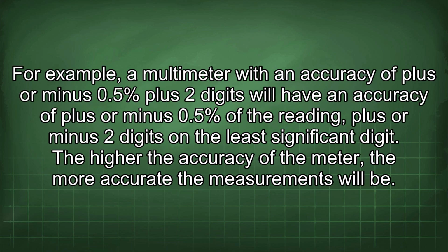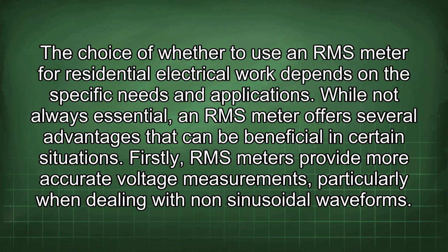For example, a multimeter with an accuracy of plus or minus 0.5% plus 2 digits will have an accuracy of plus or minus 0.5% of the reading, plus or minus 2 digits on the least significant digit. The higher the accuracy of the meter, the more accurate the measurements will be. The choice of whether to use an RMS meter for residential electrical work depends on the specific needs and applications. While not always essential, an RMS meter offers several advantages that can be beneficial in certain situations.